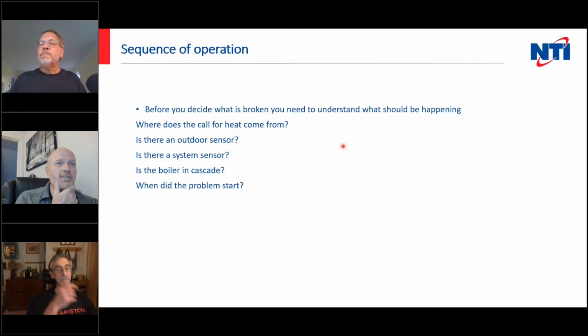So sequence of operation: the first thing you need to do any time you do troubleshooting is understand what should be happening before you decide what's wrong. We run into this a lot with new tech support guys and people that are new to the product. They have it in their head what they think should happen, and it's not really what you think that matters, it's what the boiler thinks.